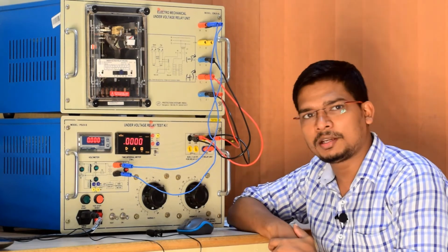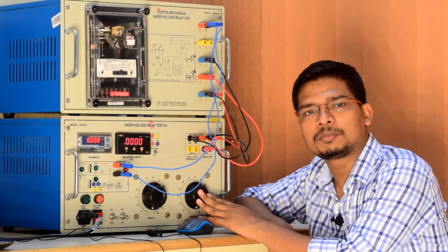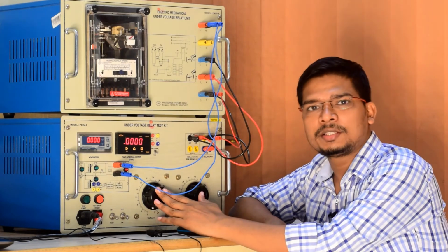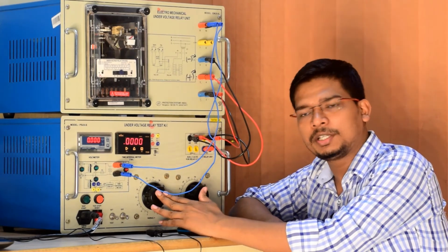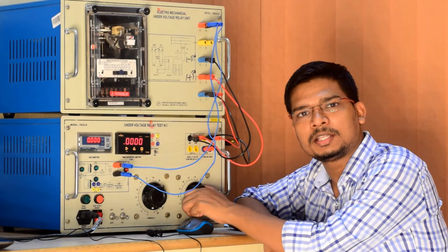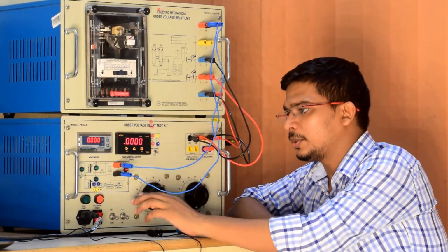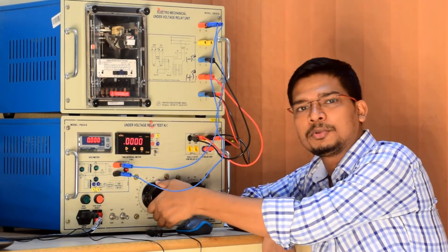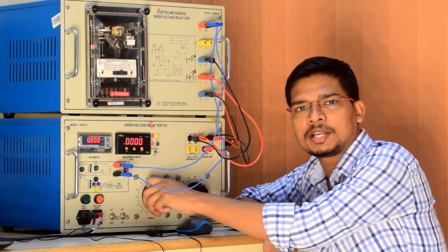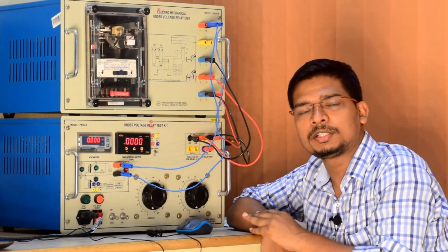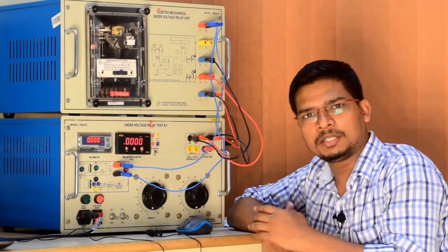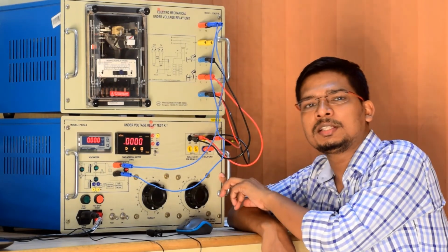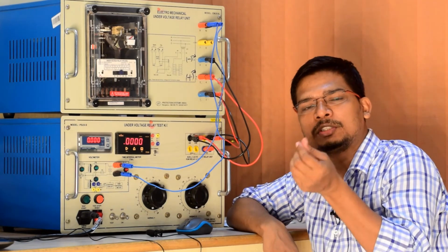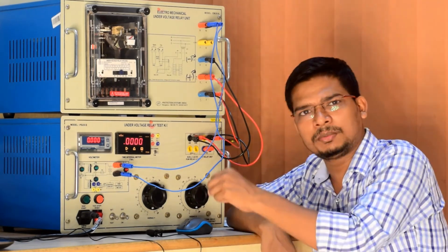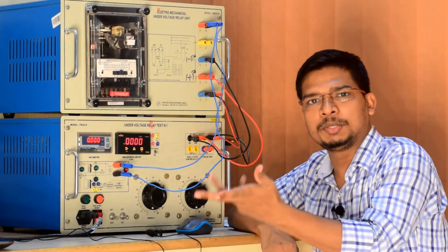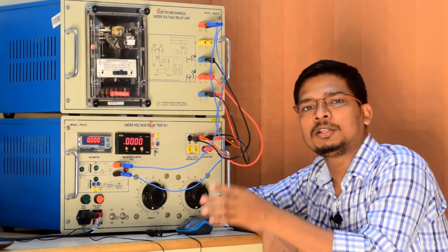So that means, as I already told you, here we are using two variacs. One variac is used to set the relay's normal operating voltage, and another variac is used to set the under voltage. So before turning on the circuit breaker, we have to give 110 volt using variac number 1, so that the relay will come to its normal operating mode. Because without giving any voltage, as this is an under voltage relay, it will sense 0 voltage, which is nothing but the trip. So if we are not giving any voltage, that means the relay will be in trip mode. So we have to make the relay be in normal operating mode.